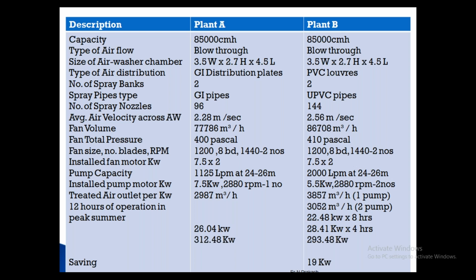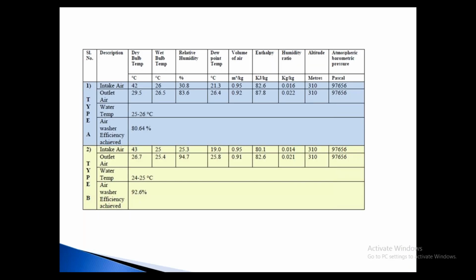It increased marginally for two pumps, but if you see how it was working, two pumps were working only for 4 hours and for the balance 8 hours a single pump was working. Because of that there was a 19 kilowatt saving over the 12 hours, morning 8 to 8 p.m. So 19 kilowatt of power was saved by the modification in the spray system. Like that, what exactly the customer requires, what pump exactly is required, this flexible operation improved the performance.